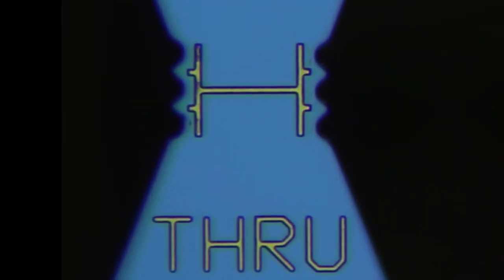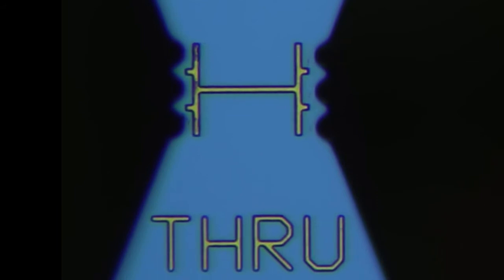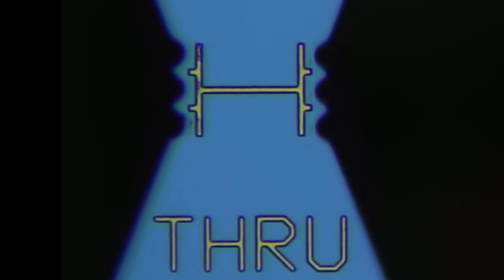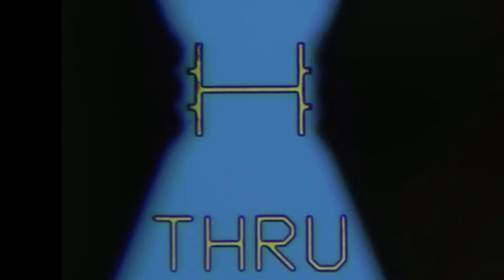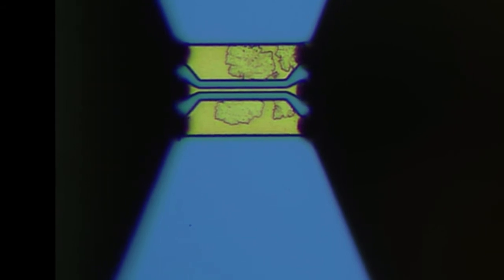We're now looking at the alignment marks for the through. All alignment marks are typically located just above the standards and we use these to set the separation distance and over travel. The little pockets that you were seeing run deep and represent the scrub distance of the probes.